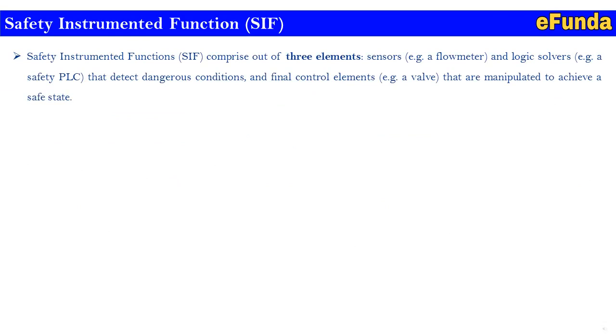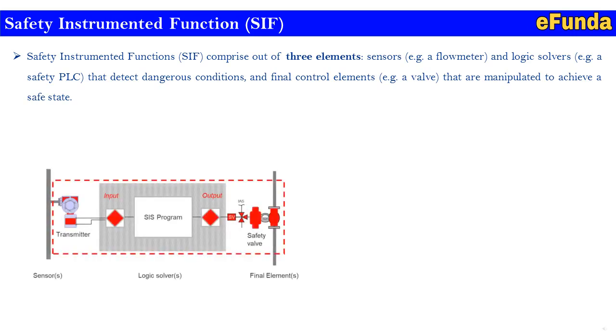Safety Instrumented Function (SIF): an SIS comprises three elements — a sensor (e.g., a flow meter), a logic solver (e.g., a safety PLC) that detects a dangerous condition, and a final control element (e.g., a valve) that is manipulated to achieve a safe state. In the first diagram, transmitters are connected as inputs to the SIS program acting as a logic solver, whose output drives the final elements such as valves.